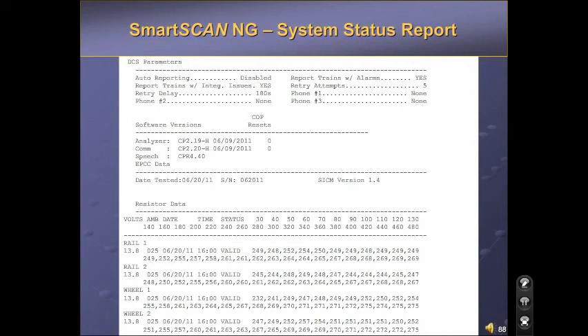There are 3 possible outcomes for the resistor table test: valid, invalid, or pending. Valid means the test was successful and the system is ready to go. Invalid means the temperatures the test expected to see are not on the table. It will try to run the test a second time. If it still fails, the label will remain invalid, and the interim test in the software will be used for post-train integrity testing. The interim test is 4 distinct time periods with fixed resistor values.